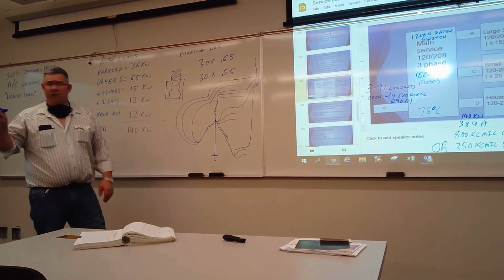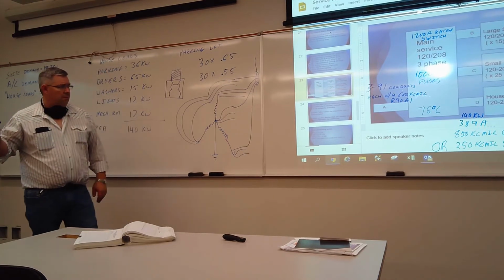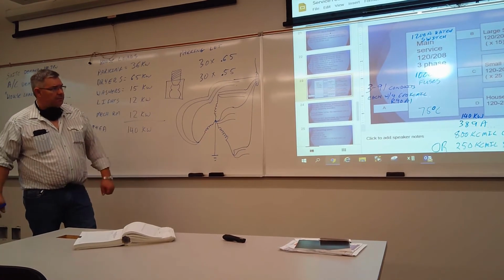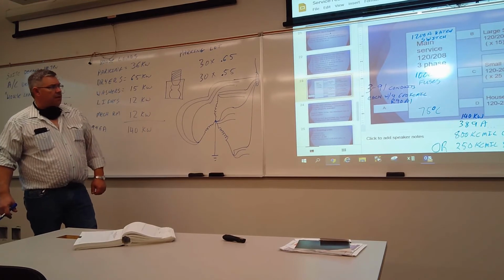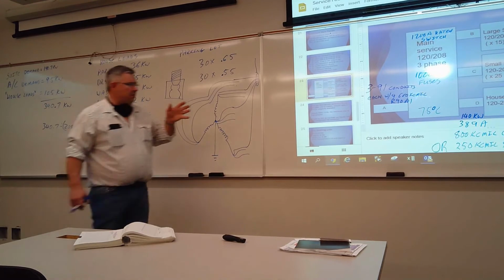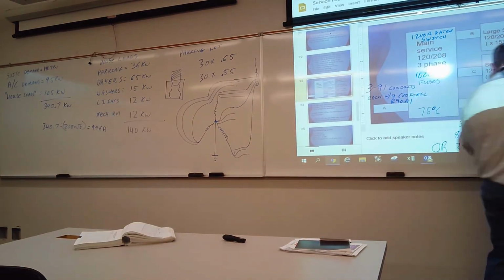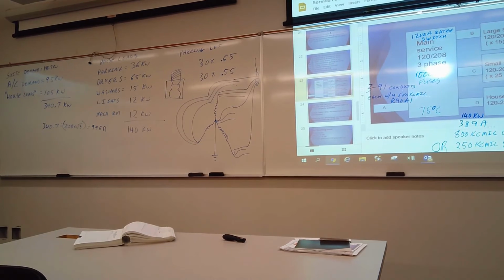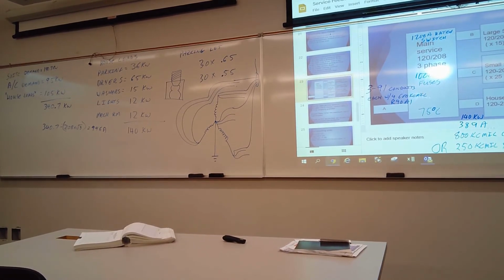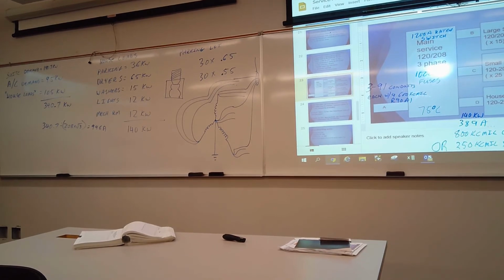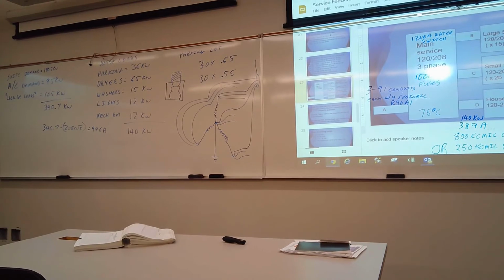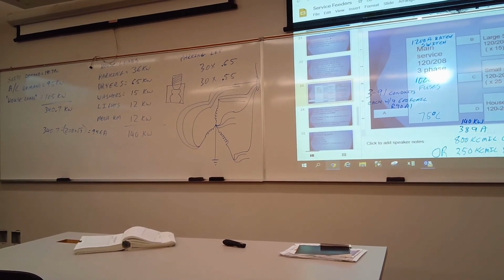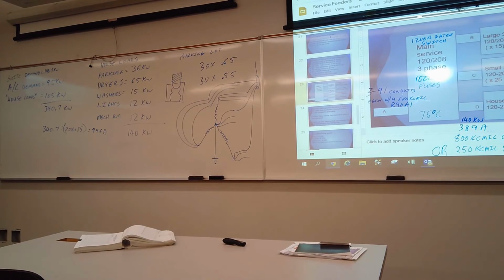I've got another slideshow I can show you. It's got that. So that's our house panel, and whether you use the 800s or the 250s, the other thing you consider is, if you come out of the splitter to your disconnect and the house panel's right next to it, well, 4 feet of 800s to put in there, not a big deal, right? If you come out to your disconnect and the house panel is quite a ways away, it might be easier to run two parallel conduits and pull the wire twice rather than run them great big fellas, right?